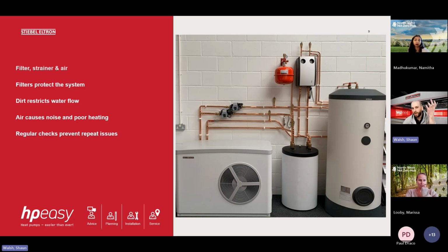And a typical result of that would be the heat pump will keep running anyway. It would probably get louder because it has to work harder to overcome the restrictions in the system, and it would be less efficient again. Okay. So it's like trying to breathe through a blocked mask. If you had a COVID mask on and you're trying to breathe through it and it was all blocked, that's basically what the heat pump will be trying to do. You could still breathe a little bit, but maybe not as effectively.